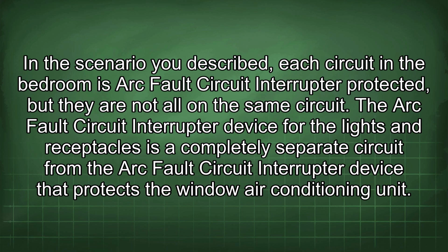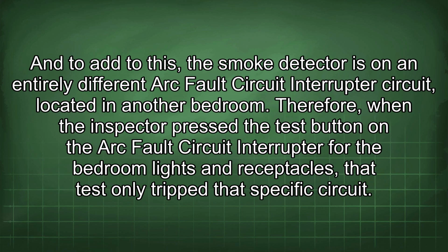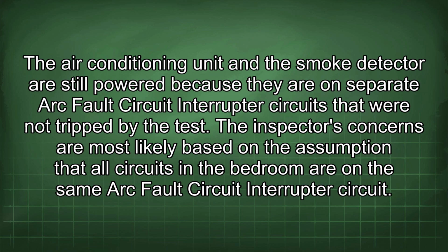The arc fault circuit interrupter device for the lights and receptacles is a completely separate circuit from the arc fault circuit interrupter device that protects the window air conditioning unit. And to add to this, the smoke detector is on an entirely different arc fault circuit interrupter circuit located in another bedroom. Therefore, when the inspector pressed the test button on the arc fault circuit interrupter for the bedroom lights and receptacles, that test only tripped that specific circuit. The air conditioning unit and the smoke detector are still powered because they are on separate arc fault circuit interrupter circuits that were not tripped by the test.